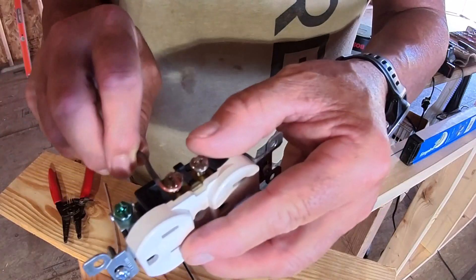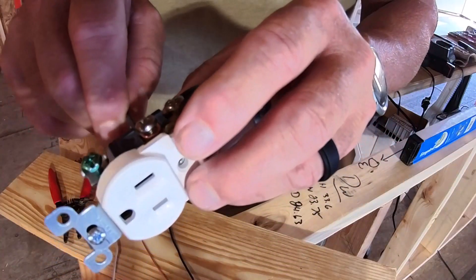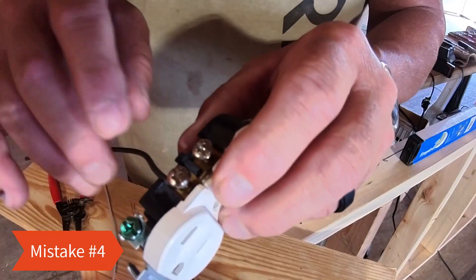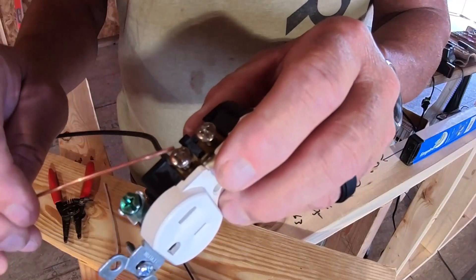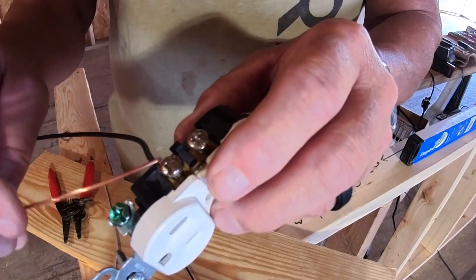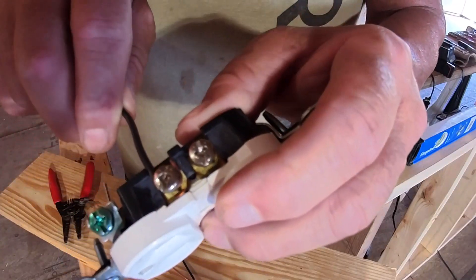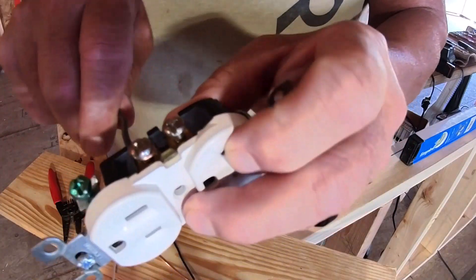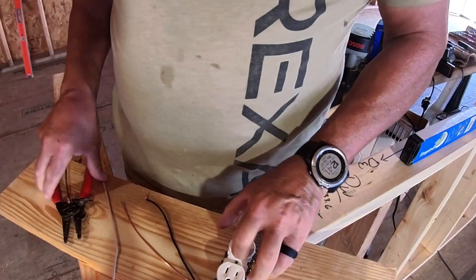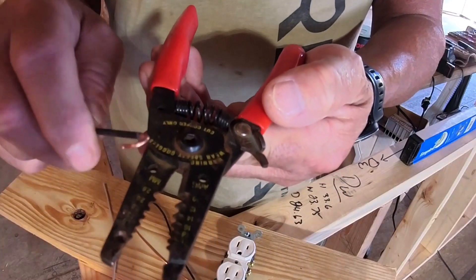That makes your perfect loop. Mistake four is having too much insulation stripped. If the insulation is stripped past the screw area, you have a good chance of that bare wire connecting with a ground wire and shorting that circuit out. A perfect loop covers inside the screw area. Whenever you're using your wire strippers, use that loop tool to get your perfect loop.